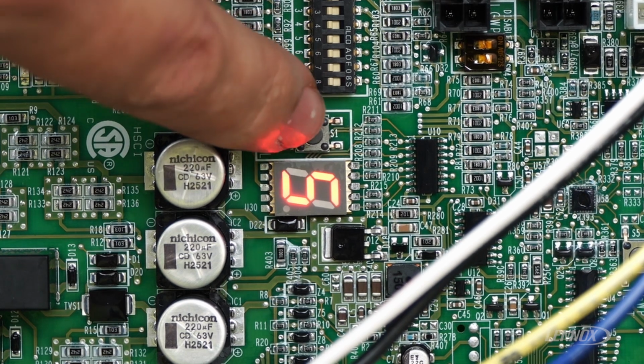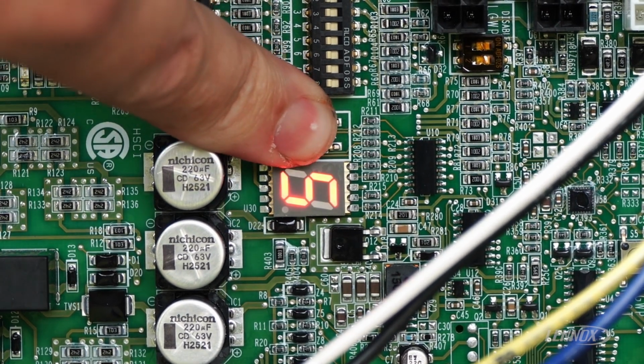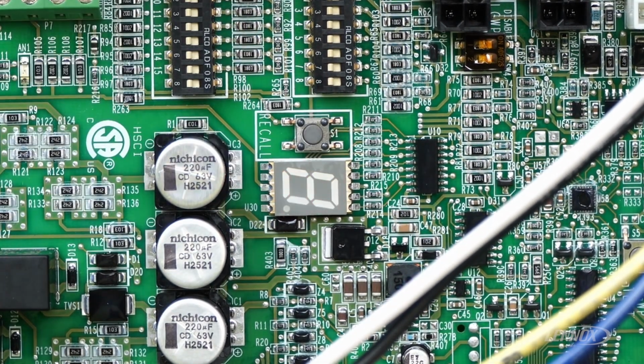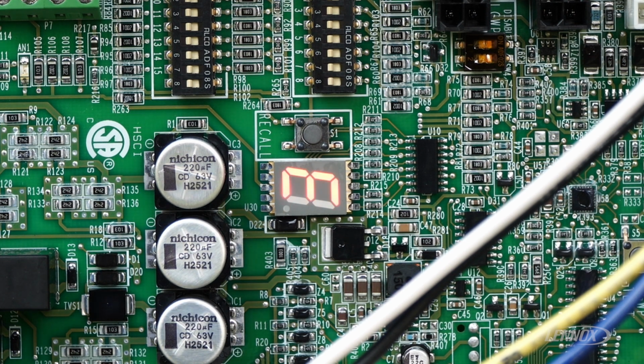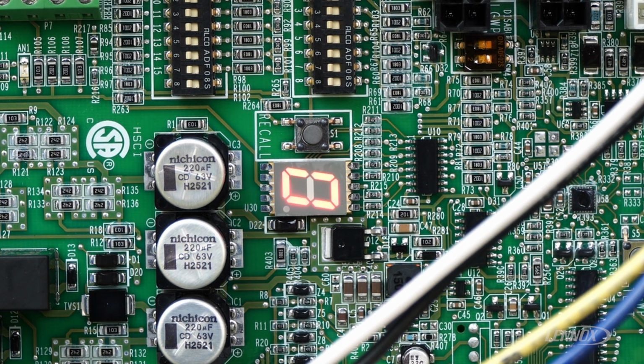When we get to 5, we release. When 5 is flashing, push and hold - you'll hear a relay click on the board. Release again, and it's going to spit out the unit size we just programmed it for. As it tries to cycle back to a steady heartbeat, we populate an error code: E202. Error code 202 is blower motor mismatch to control.